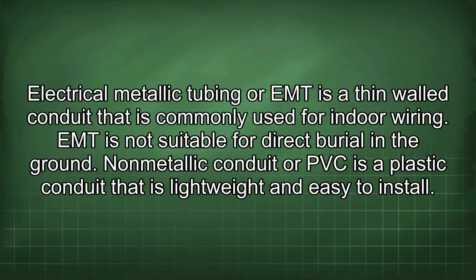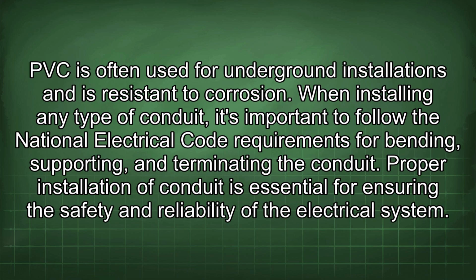Electrical metallic tubing or EMT is a thin-walled conduit that is commonly used for indoor wiring. EMT is not suitable for direct burial in the ground. Non-metallic conduit or PVC is a plastic conduit that is lightweight and easy to install. PVC is often used for underground installations and is resistant to corrosion.